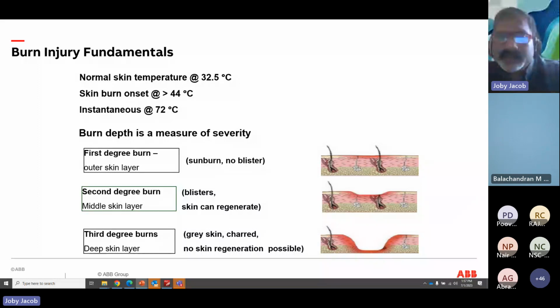What is a second degree burn? For example, a candle burn or candle wax falling on you. Your outer skin blows up and you have blisters. After a few days, your skin can regenerate. But normally, in a real arc flash, you get second and third degree burns. In third degree burns, your deep skin is completely charred. No skin regeneration is possible, so you may need to graft skin from another part of the body. And if it is too much, that is not possible either.